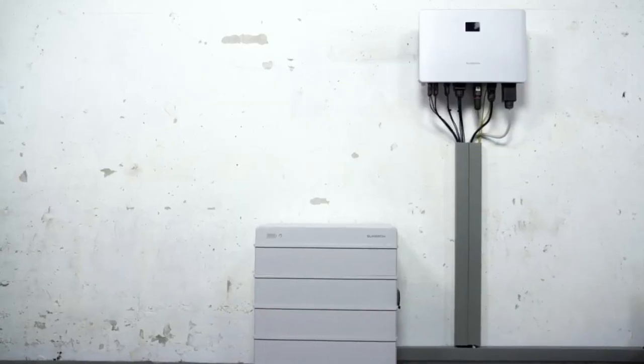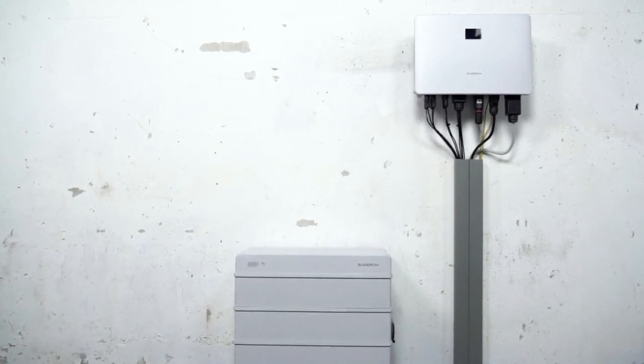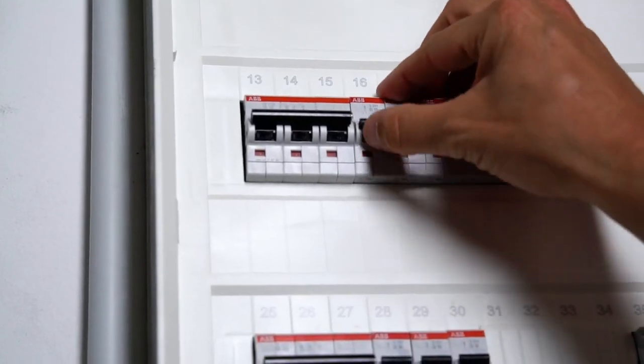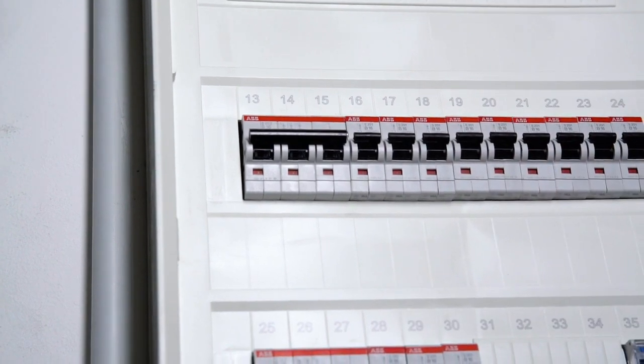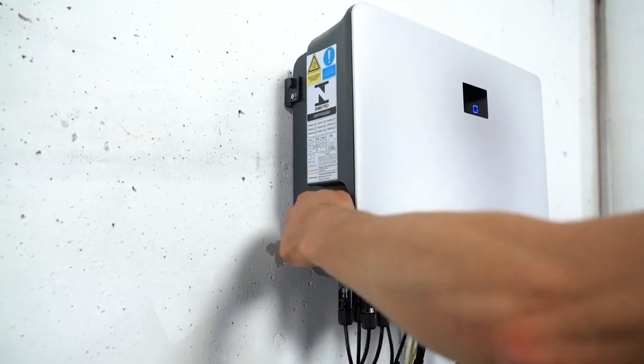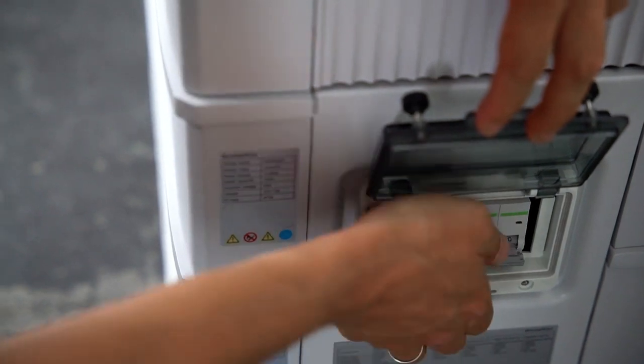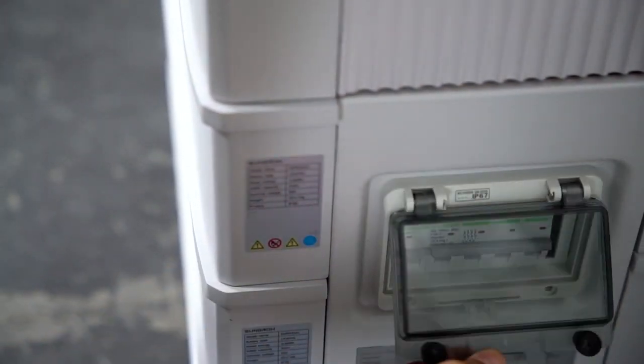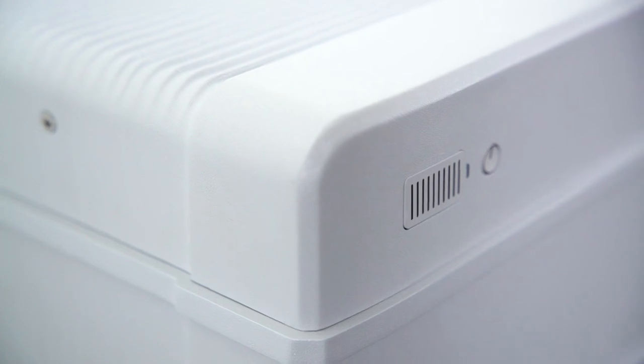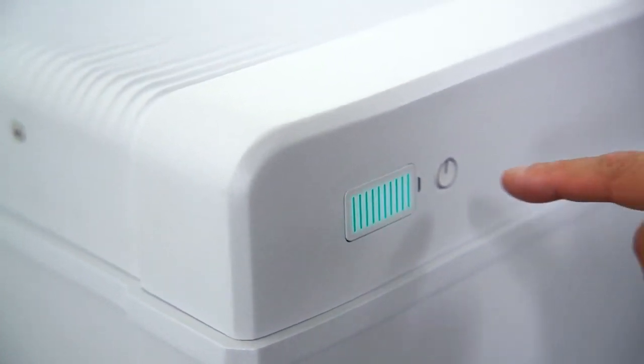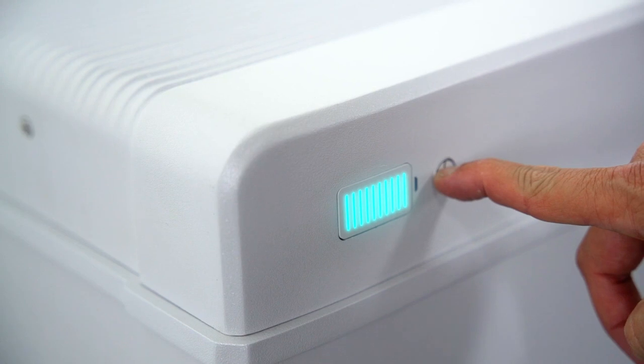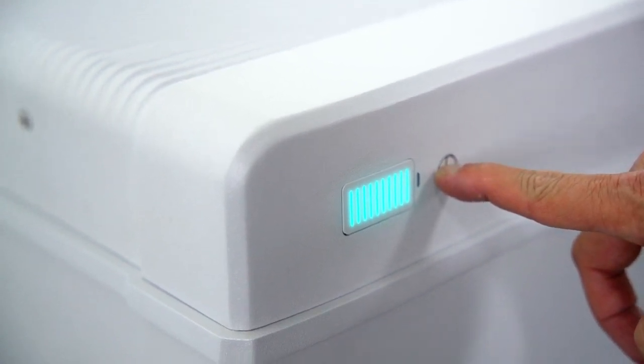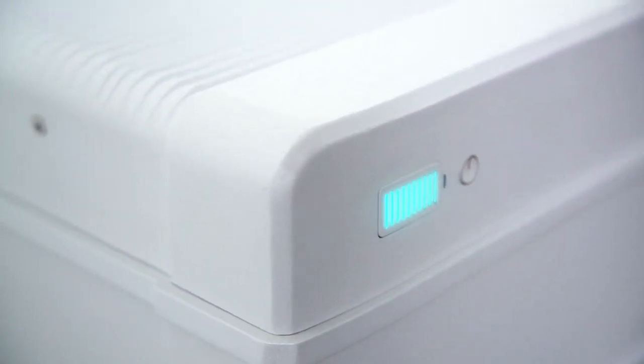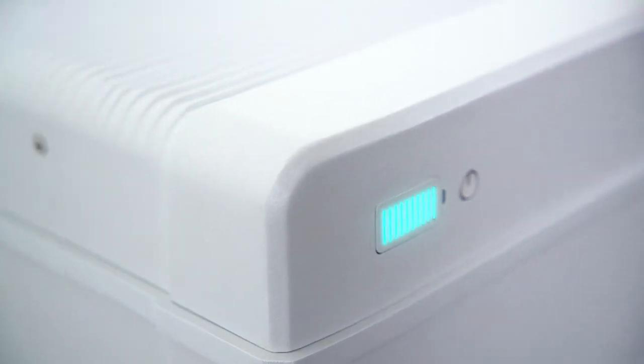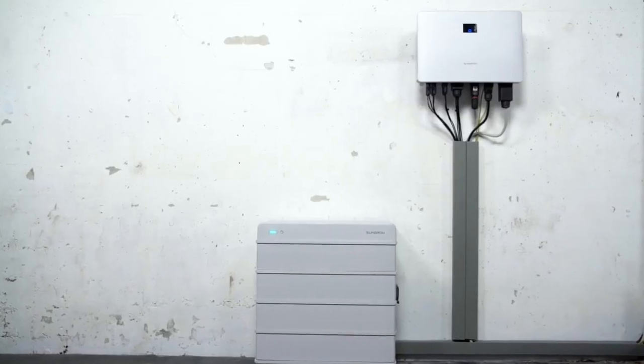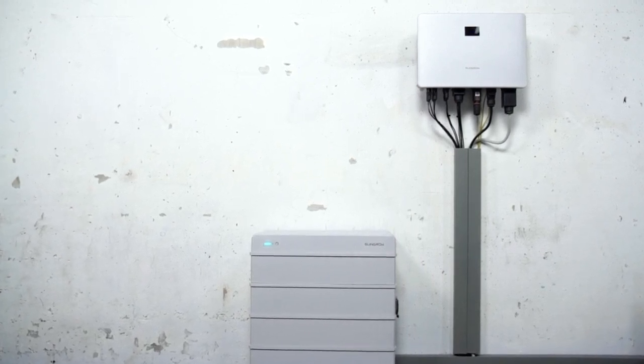Beyond the expected. Now it's time to start the system. First, switch on the AC circuit breaker and second, the DC circuit breaker on the left side of the inverter and on the right side of the battery. Wait for about 10 seconds till the status LED on the battery starts blinking. Press the power button once. When the light shines continuously, the battery is ready for use. If this is not the case, please refer to the manual, where you will find a breakdown of the different light signals. That was it. The system is ready to run.